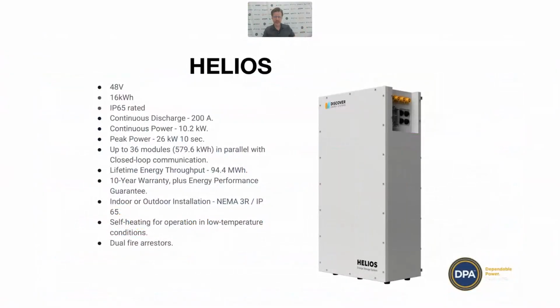Just to go over the Helios for those of you who aren't familiar with it: it's a 48 volt battery, 16 kilowatt hours, IP65 rated so it can go indoor and outdoor. It's rated at 200 amps continuous charge and discharge, though I wouldn't recommend you run it at that spec. I wouldn't recommend you run anything at the top spec. Peak power is 26 kilowatts for 10 seconds.